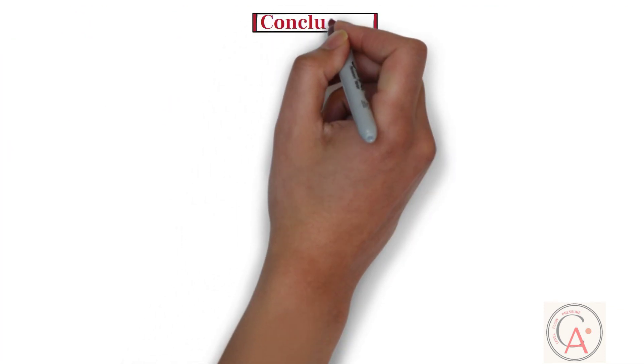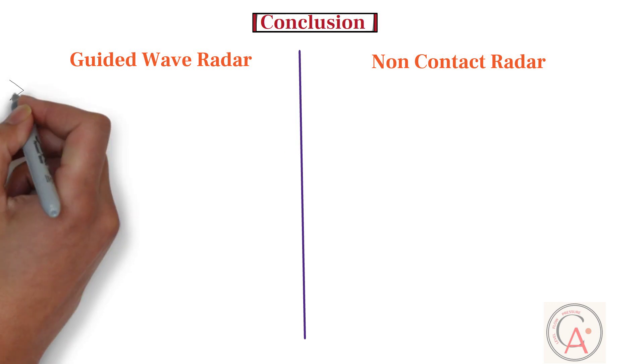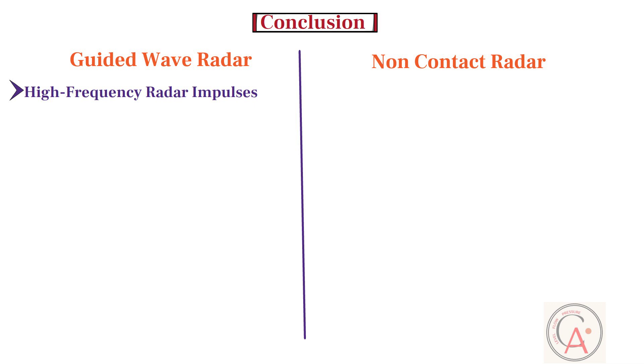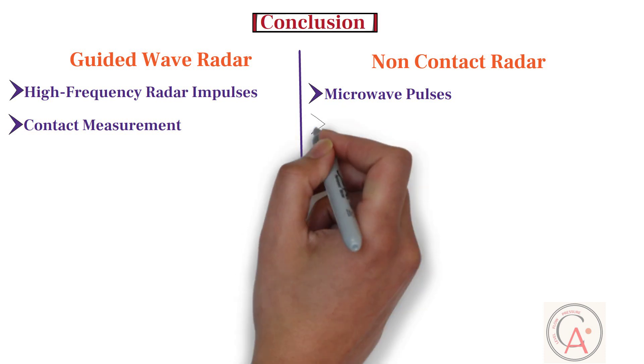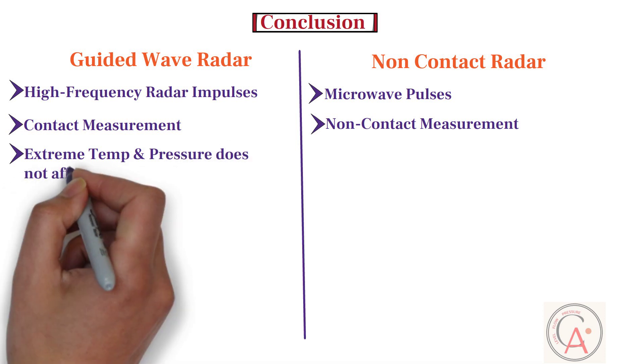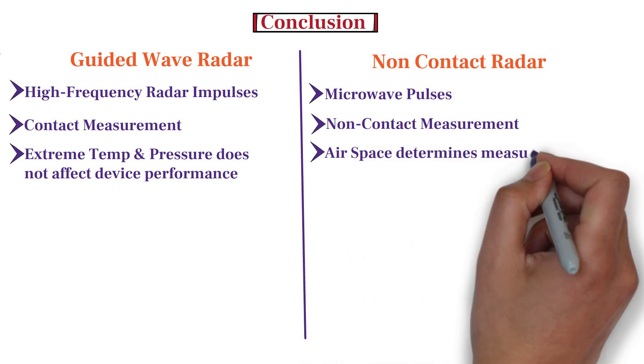In the last part of this video, I will compare both technologies. Firstly, guided wave radar technology uses high-frequency radar impulses for level measurement, while non-contact radar level technology uses microwave pulses. Secondly, guided wave radar is a contact type level measurement technique, whereas pulse radar is a non-contact technique. In addition, guided wave radar level measurement is not affected by extreme temperature and pressure, while the air space determines the measurement accuracy of pulse radar, making it not ideal for extremely difficult applications.